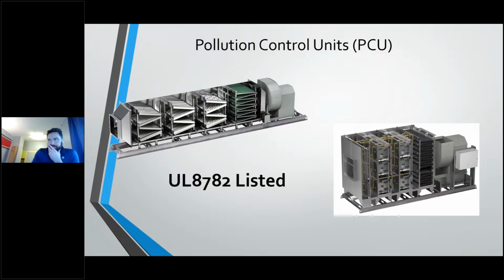Finally, pollution control units. Once you accomplish grease extraction, even if you have 70 to 80% grease extraction, there's still going to be grease escaping into that system. There are three ways that pollution control units are operated, to my knowledge. I can speak to the two that I know the best, but there's also UV in the industry, which different manufacturers will utilize for pollution control units. What I can speak to is either a filtered unit or an electrostatic precipitator unit.